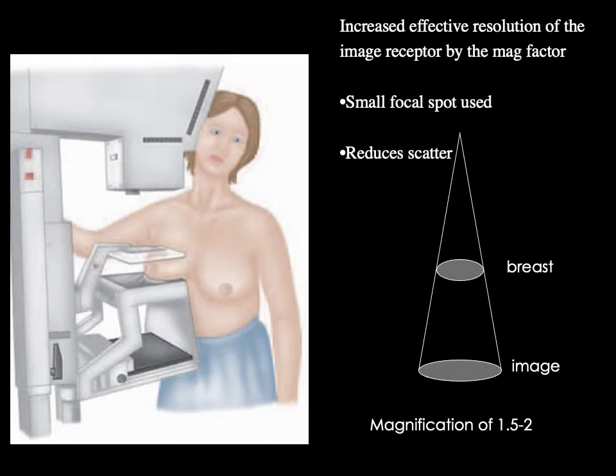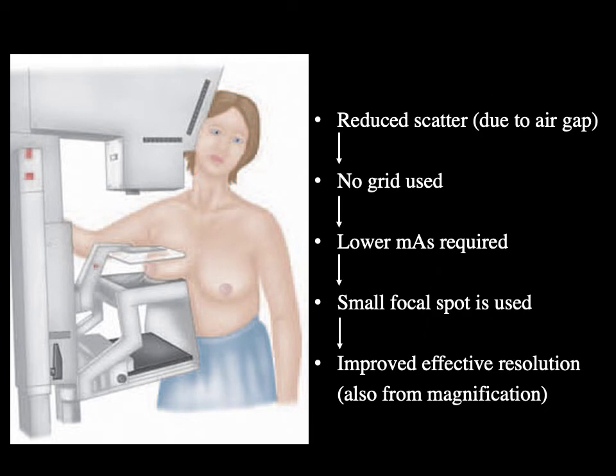Mammography can also be performed in magnification mode using geometric magnification. A stand is placed above the image detector and the breast is placed on top of this stand. A smaller focal spot is used, and the air gap between the magnification stand and the image detector not only magnifies the image by a factor between 1.5 and 2, but also reduces the amount of scatter reaching the detector. Because the air gap reduces scatter, no grid is used, which lowers the mAs required and allows a small focal spot, helping to improve effective resolution.